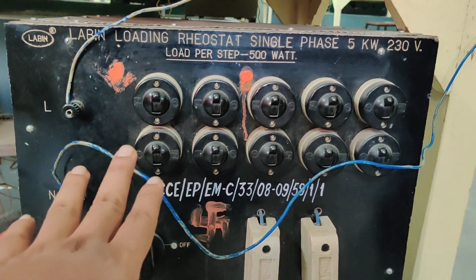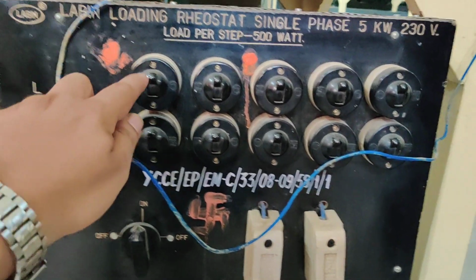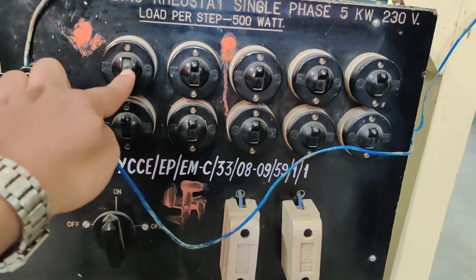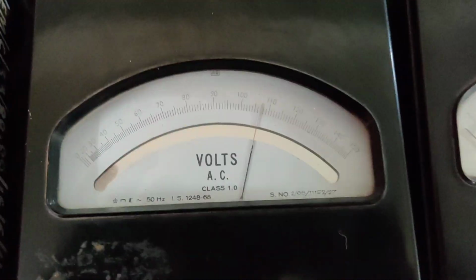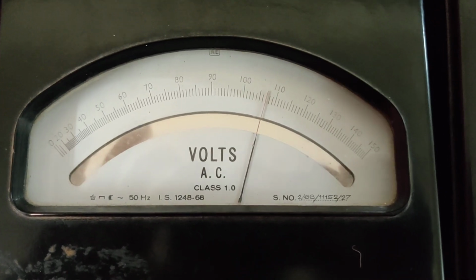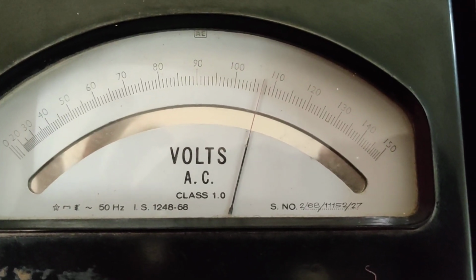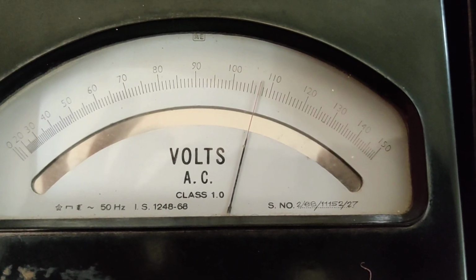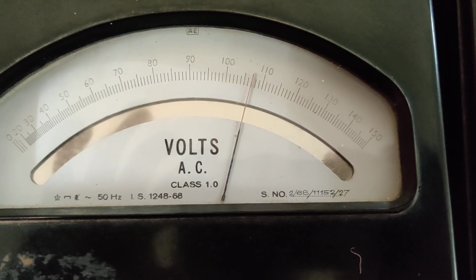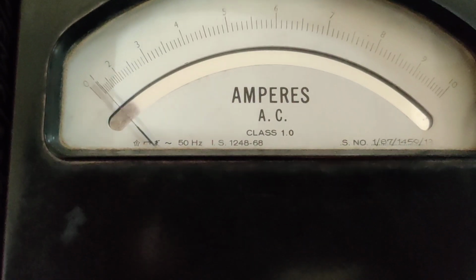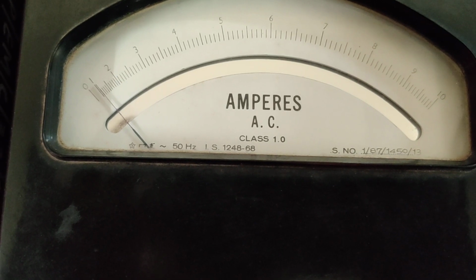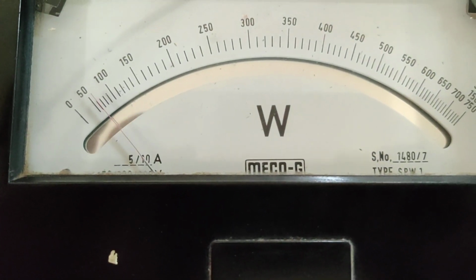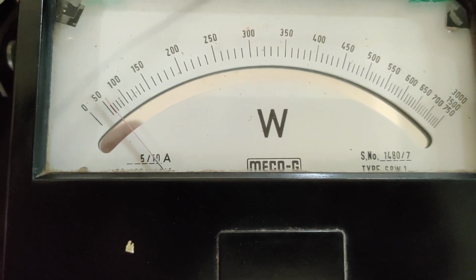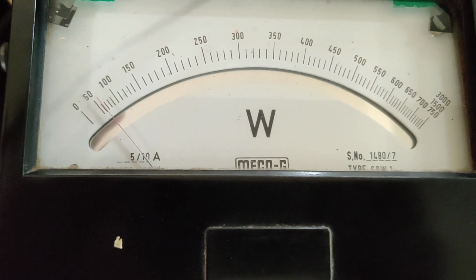So we already took the no load reading. Now talking about the load reading, if I switch on one switch, what will happen? On the secondary side, a small voltage drop will occur. Earlier it was 108 volts, now it is 107 volts. Now some current will show, approximately 1 ampere, and here the voltage is given. So on the secondary side we have current and voltage, that is why we have power.